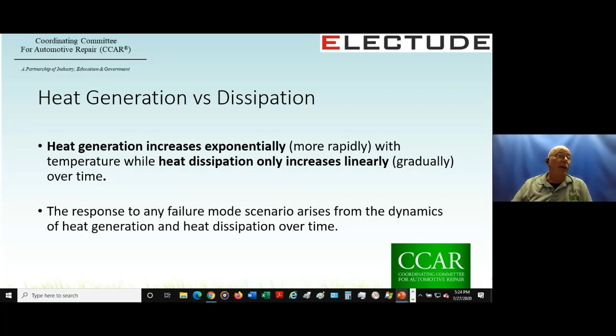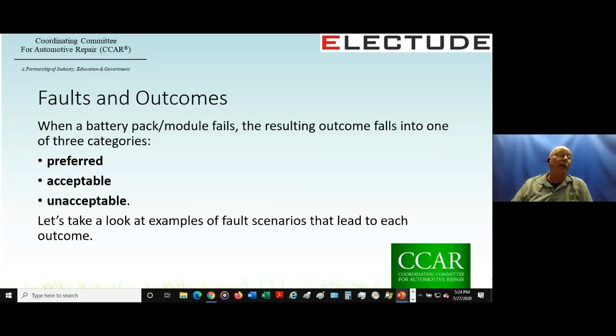So faults and outcomes. When a battery pack or module fails, the resulting outcome will fall into one of three categories: preferred, unacceptable, and acceptable. We're going to take a quick look at each one to see what those scenarios might look like. First up is the preferred outcome. In this case, we'll describe it as a failure that occurs within the cell that leads to an increase in temperature. Pick the favorite failure that you like. I happen to like short circuit. A reaction within the cell creates additional heat and gas and the reaction zone expands. But in this particular instance, the heat dissipation rate exceeds the generation rate over time and the cell is cooled. A benign temporary thermal event, no thermal runaway.